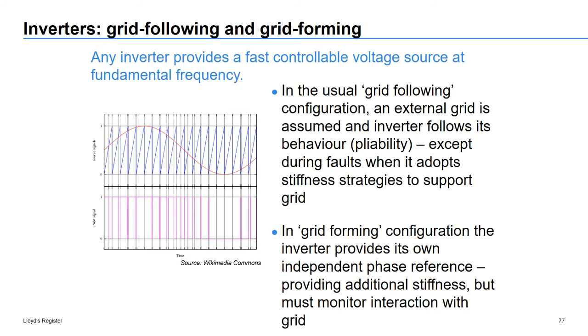the requirements on these inverters also emphasise the need to provide stiffness to support the network under extreme operating conditions such as faults. And in that case, grid following inverters need to be programmed to inject a certain amount of fault current. But that amount needs to be determined very carefully because, as mentioned earlier, it's a very delicate balancing act between providing the required stiffness and not destabilising the network.